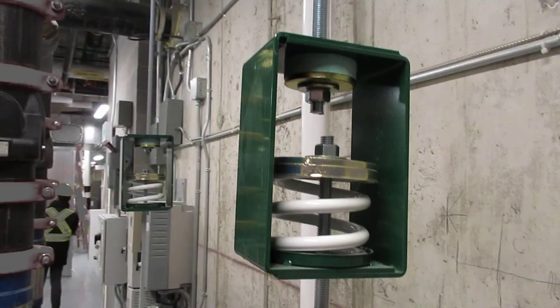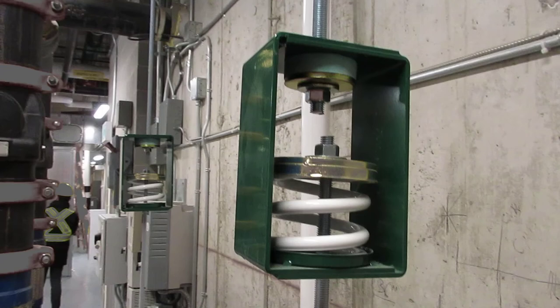This project did not have any seismic restraint requirements, so there are no uplift stop washers to inspect here. If there were, we would also be checking for a quarter inch gap and a pair of jam nuts below the stop washer holding it in place.